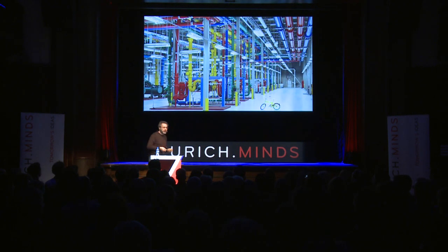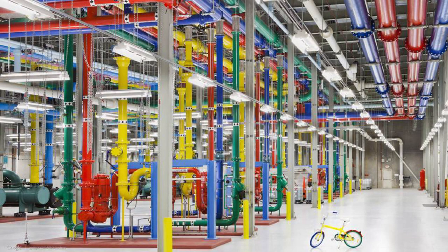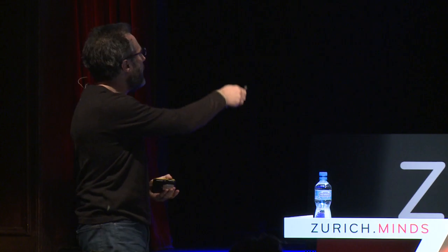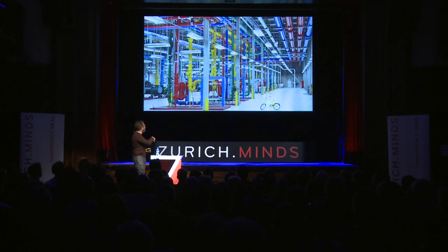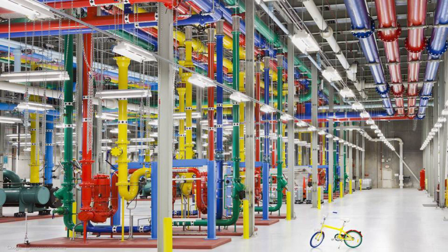Here's another system in a data center in the US, near Atlanta. And for scale, you see a Google bike, which you actually need to get around in the building because it's kind of large. Here again, basically, you see pipes. The red and blue ones come from the floor. Red is warm, blue is cold. So blue is going out to the floor, red is coming back from the floor. And then, mostly you should pay attention to the green and yellow. Those are the ones that remove the heat to cooling towers.